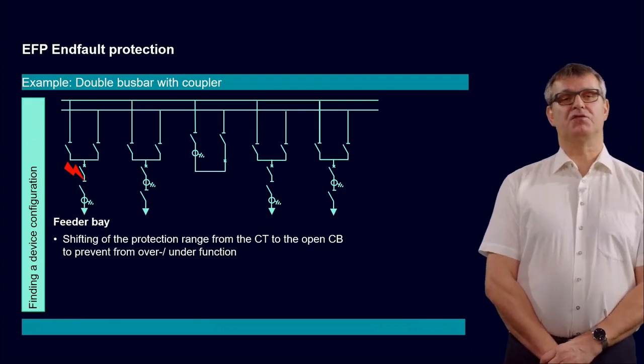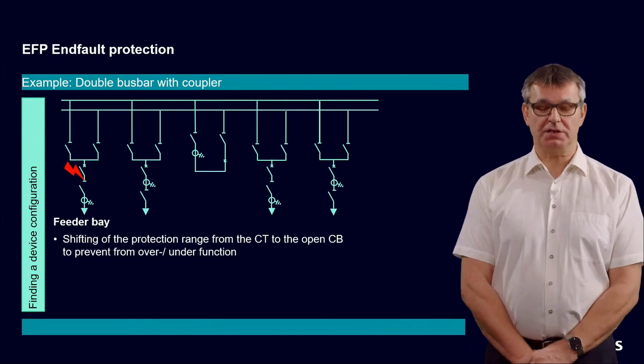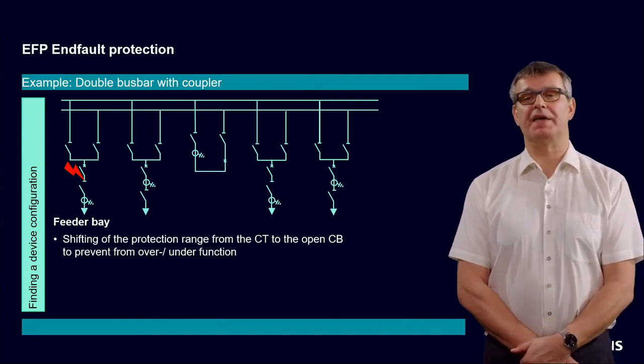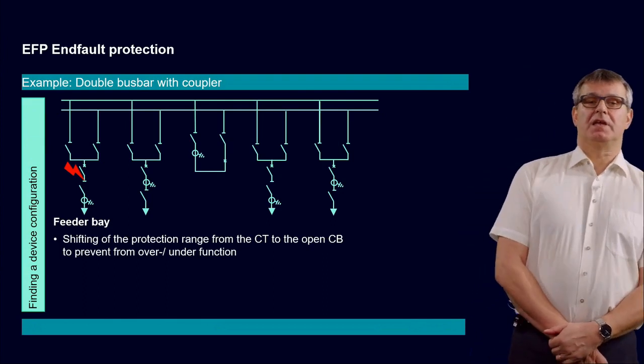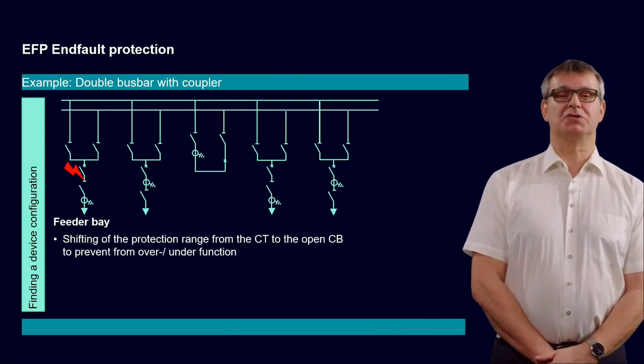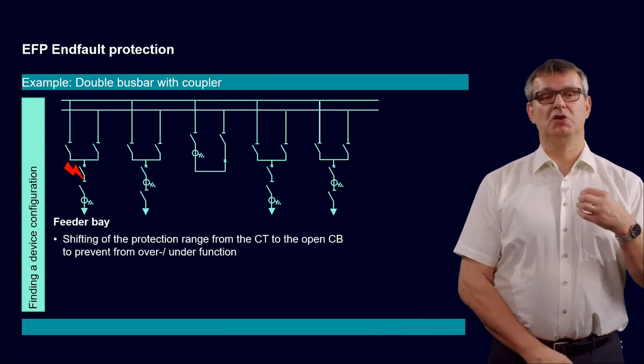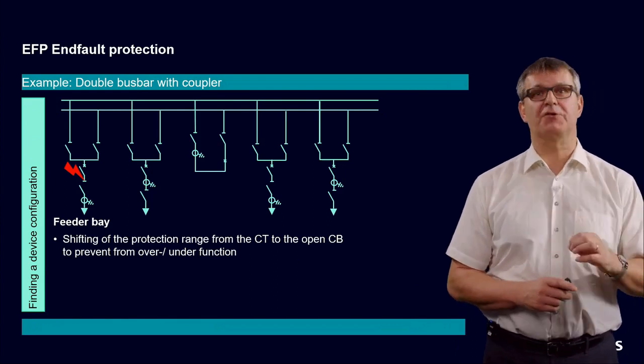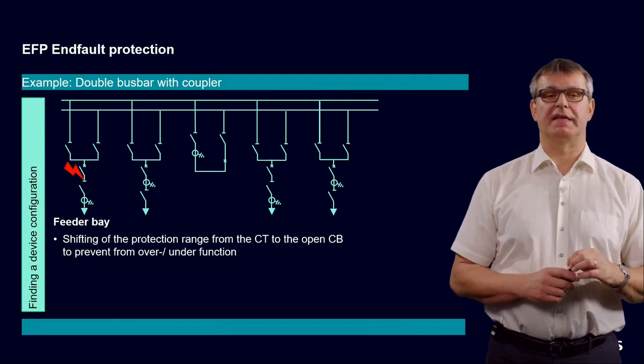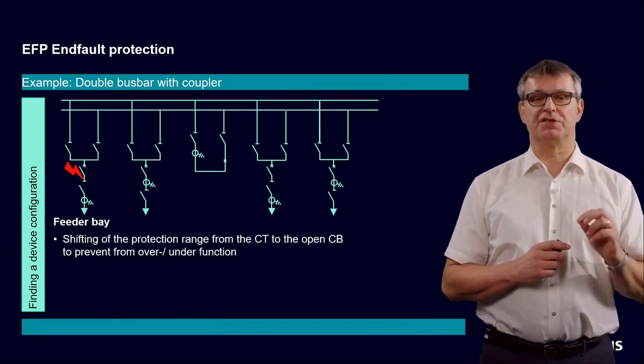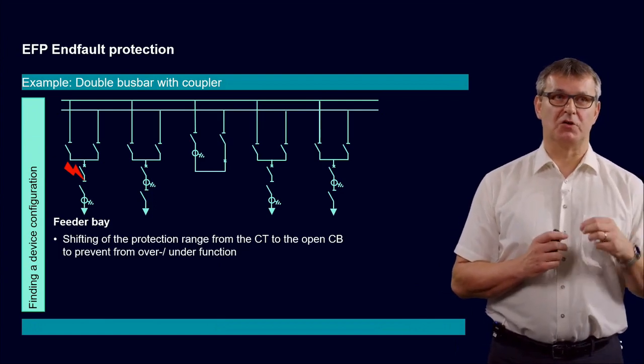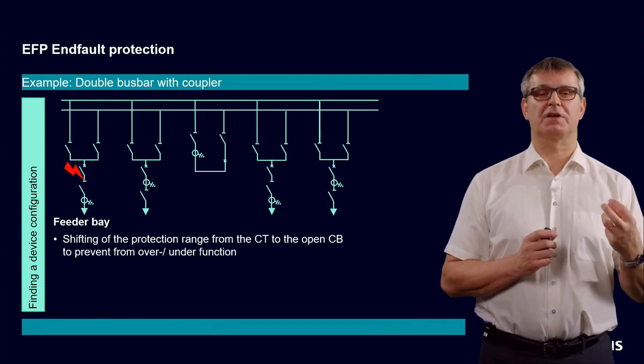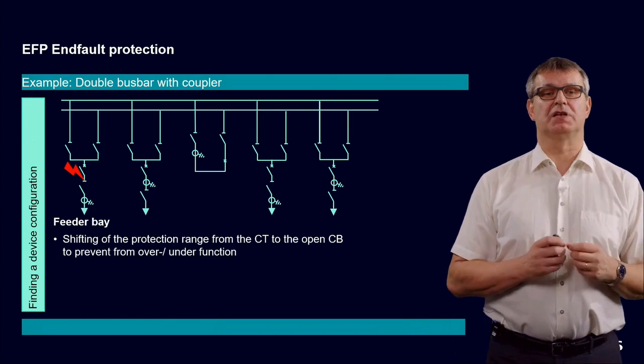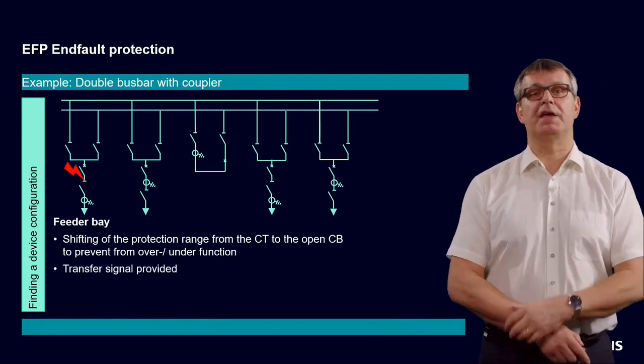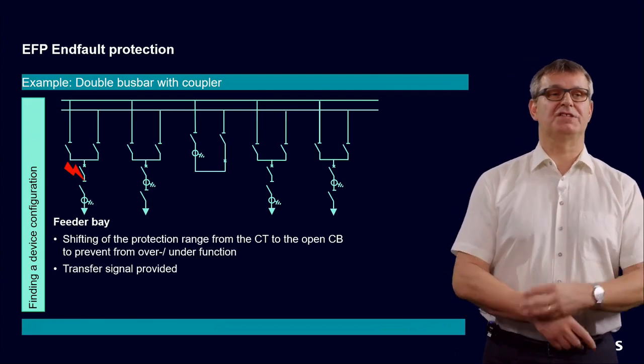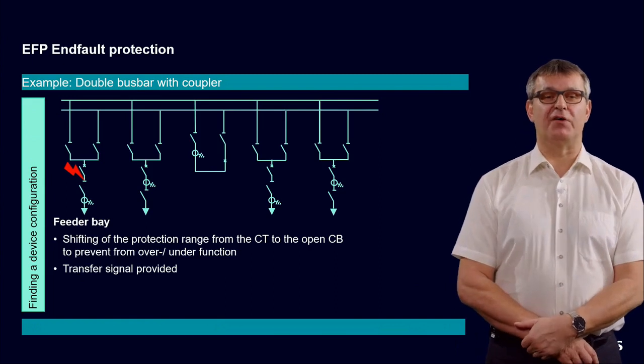End-fault protection: we have to know whether we need end-fault protection or not, because we have to pay function points for the end-fault protection functionality. Once again, an outlook to our next tutorial: the end-fault protection will shift the protection range from the current transformer to the open circuit breaker. This depends on the location of the CT, the location of the circuit breaker relative to the CD. It prevents an over- or under-functionality. That's for the feeder bay, and in the feeder bay it also gives us a transfer signal to the other end of the line to clear the fault from the other end of the line.